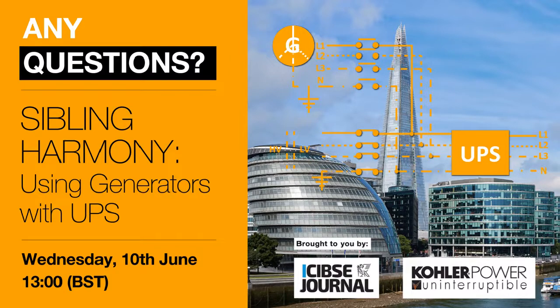Yeah. Okay, thank you very much. Interesting question here from Ian. Ian asks, what design considerations are there for using a UPS to back up lifts or elevators? Oh, okay. Depends on the lifts and the elevators. It depends how they run. But typically, you're going to have inrush current and locked rotor, fault loads to consider.